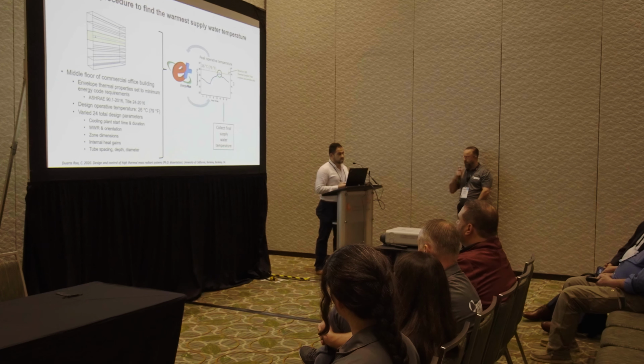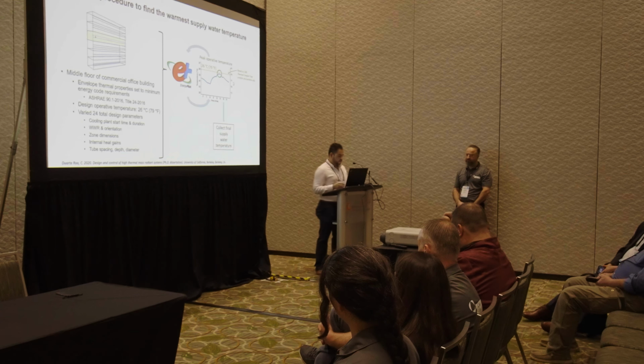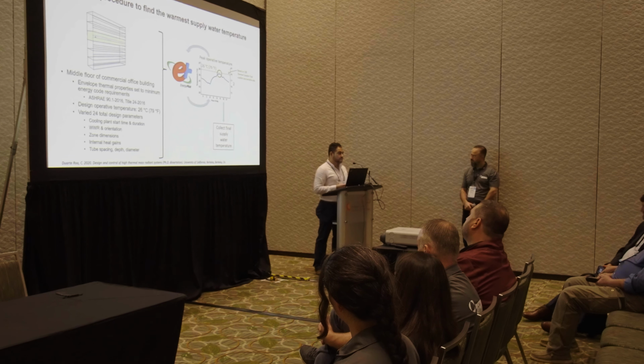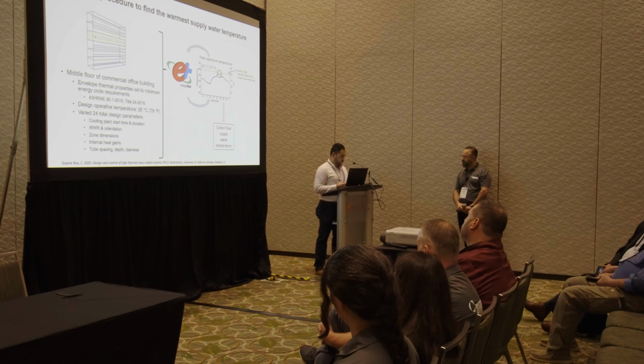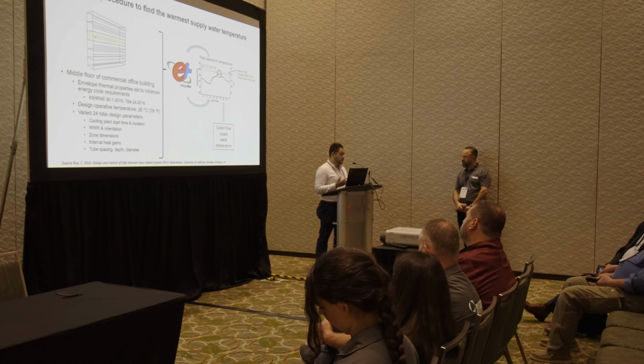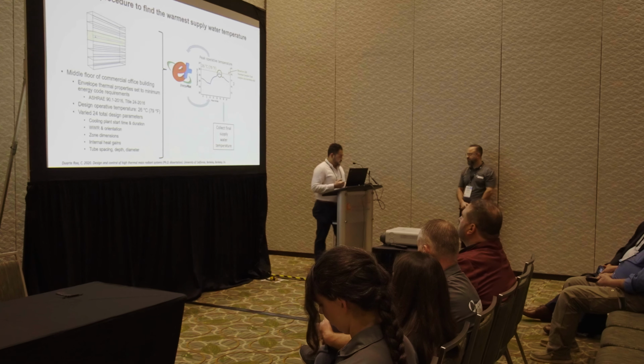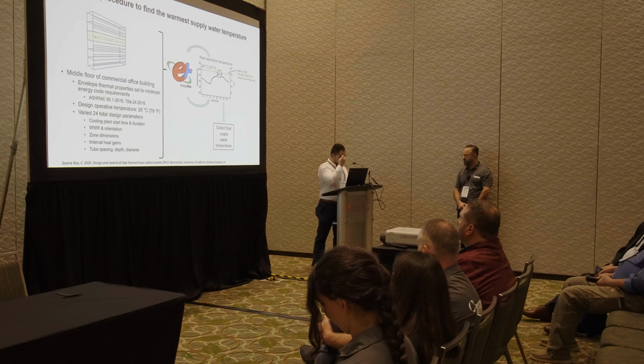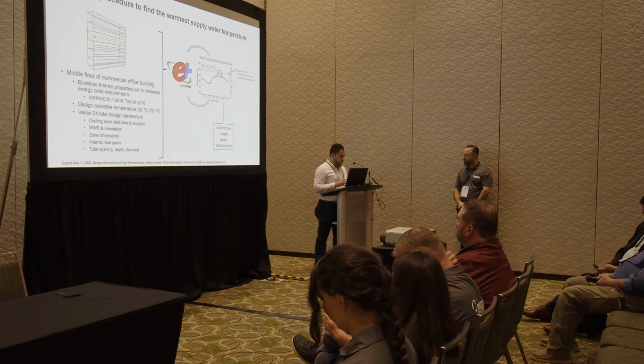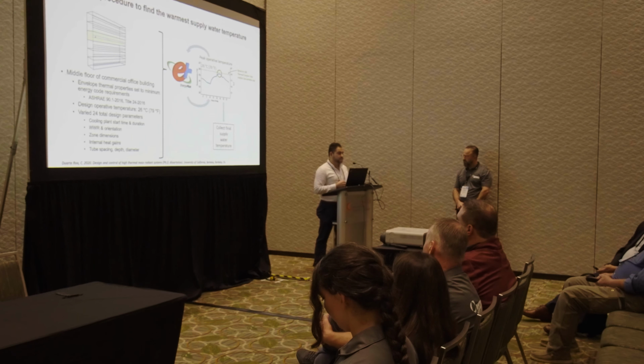And EnergyPlus is a research-grade tool. It's free and open source, and it's been thoroughly validated. So we have good confidence there's high fidelity in the results. After each simulation, we extracted the peak operative temperatures. And if the peak operative temperatures were not at 78 degrees Fahrenheit, which is our calculated upper thermal comfort bound, using the CBE comfort tool, which I'm going to talk a little bit about in later slides, then we would adjust the supply water temperature and rerun the simulation. And after this process was complete, we collected all the final supply water temperatures for each design variant to do further analysis.